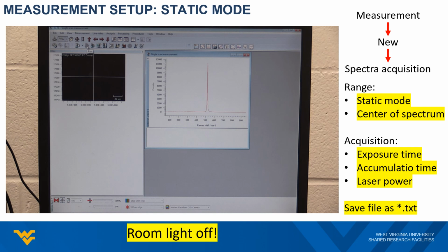Here I need to point out that if you want to make another measurement using the same parameters, you do not need to create a new window through the Measurement tab. Instead, you could just go to the existing acquisition window and run the measurement again. Then, the newly acquired spectra will be plotted in the same window on top with the previously saved spectra. Also, when you make Raman measurement, you will need to turn off the room light, so that will prevent the light contamination to your Raman spectra.